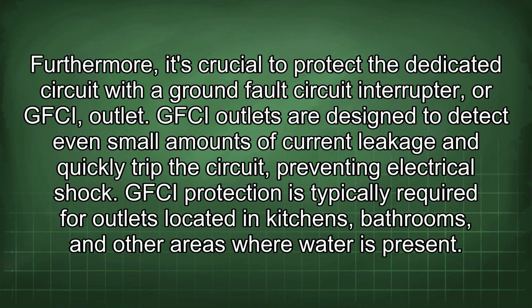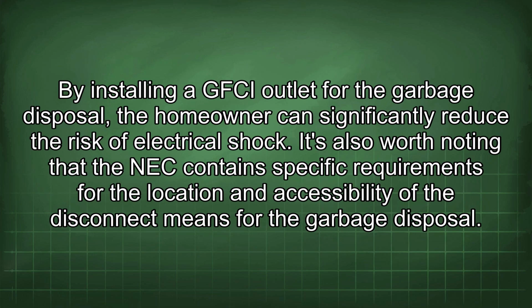Furthermore, it's crucial to protect the dedicated circuit with a ground fault circuit interrupter, or GFCI, outlet. GFCI outlets are designed to detect even small amounts of current leakage and quickly trip the circuit, preventing an electrical shock. GFCI protection is typically required for outlets located in kitchens, bathrooms, and other areas where water is present. By installing a GFCI outlet for the garbage disposal, the homeowner can significantly reduce the risk of electrical shock.